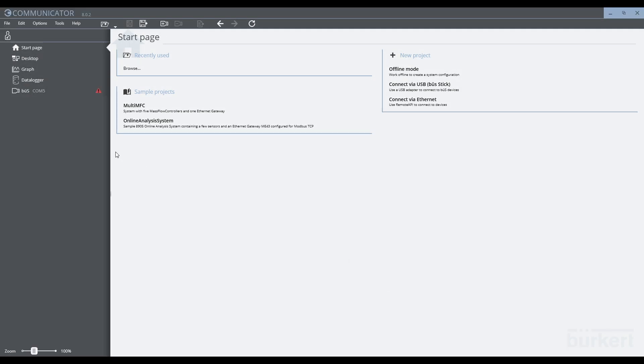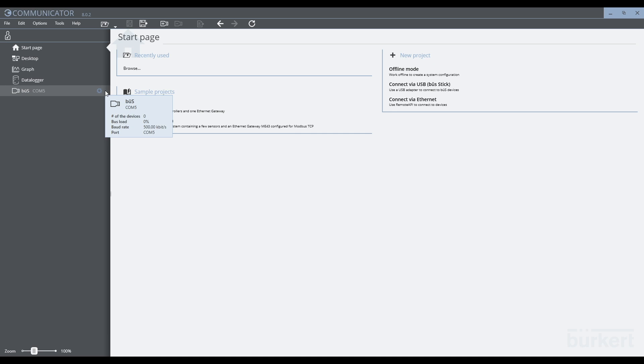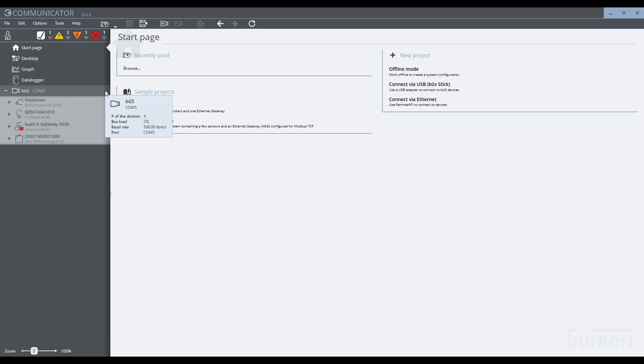When trying to search for the devices, we see the communicator has found an error. There are a couple of reasons for this: possibly no devices connected, the wrong baud rate, or no terminating resistors in the network. Be sure to check all of these factors. For now, I can see I have a loose cable. Once I connect this, communicator will search for the devices one by one, and they will appear in communicator.